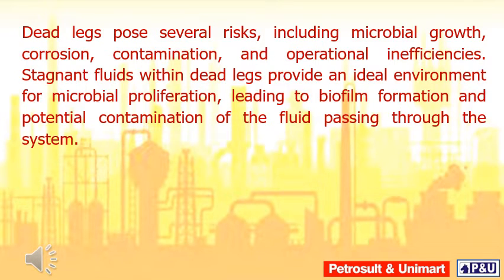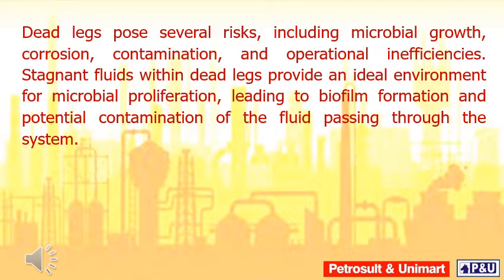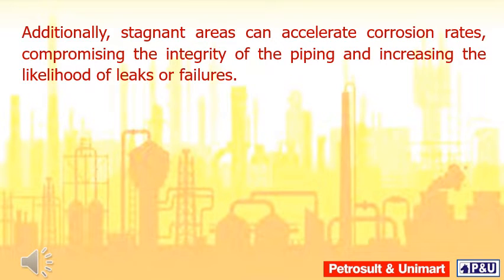Dead legs pose several risks including microbial growth, corrosion, contamination, and operational inefficiencies. Stagnant fluids within dead legs provide an ideal environment for microbial proliferation, leading to biofilm formation and potential contamination of the fluid passing through the system. Additionally, stagnant areas can accelerate corrosion rates, compromising the integrity of the piping and increasing the likelihood of leaks or failures.